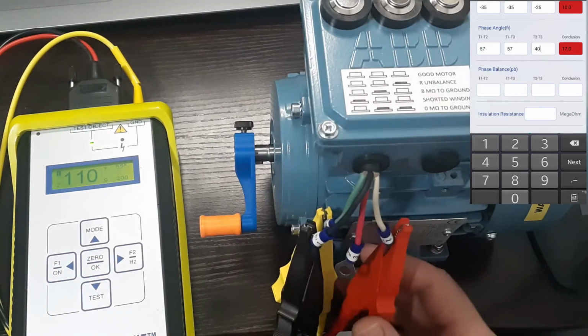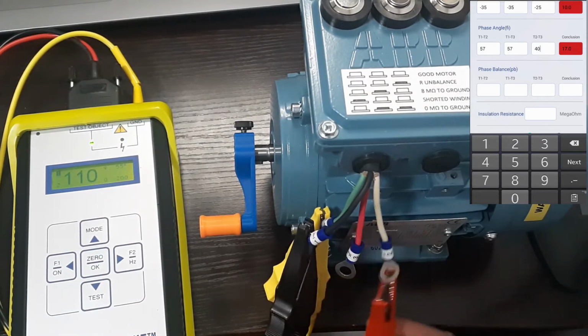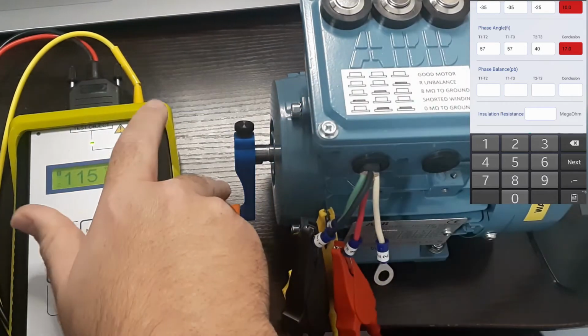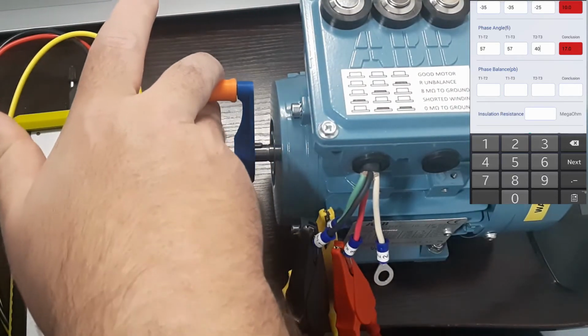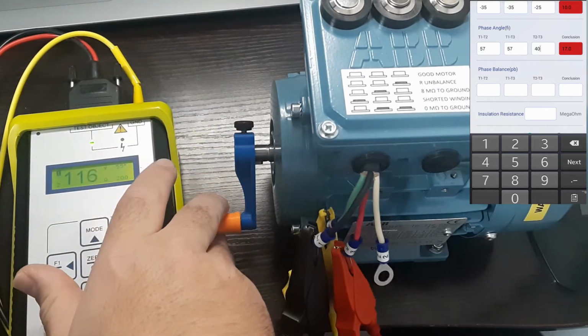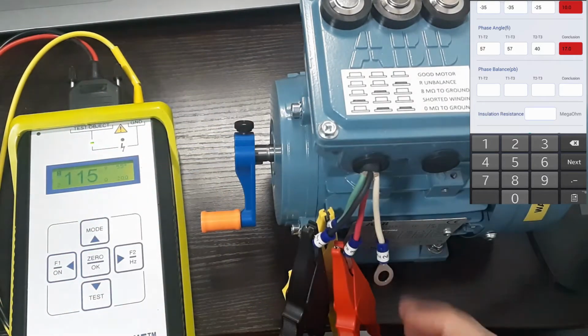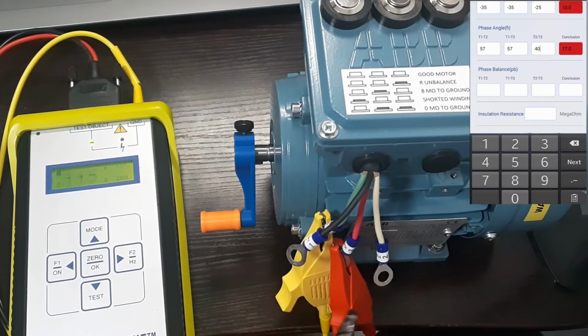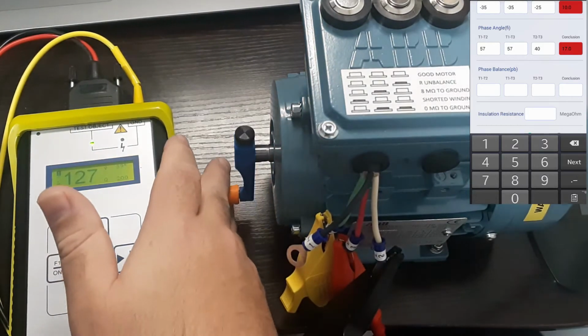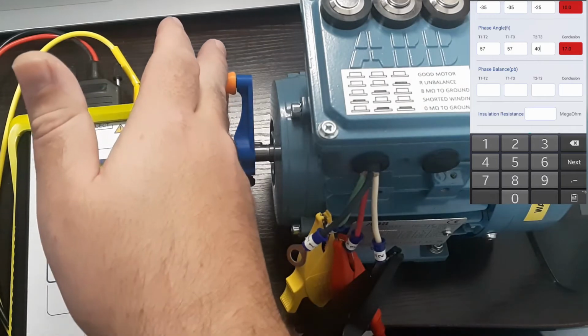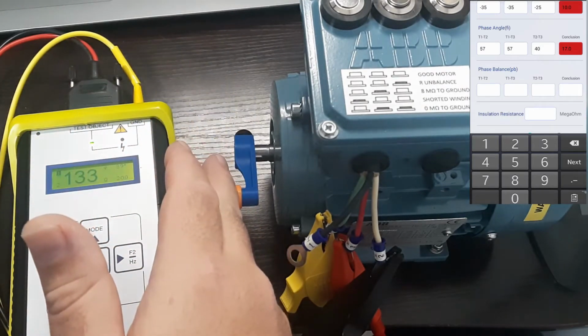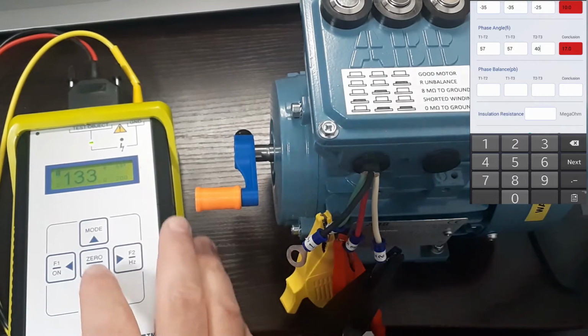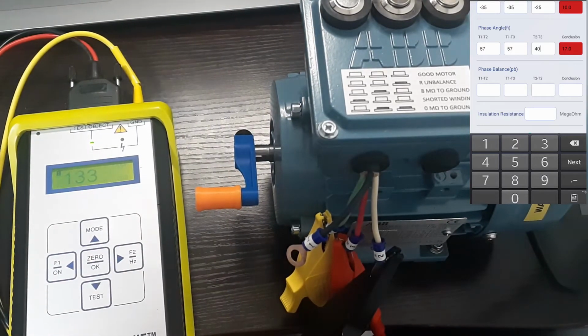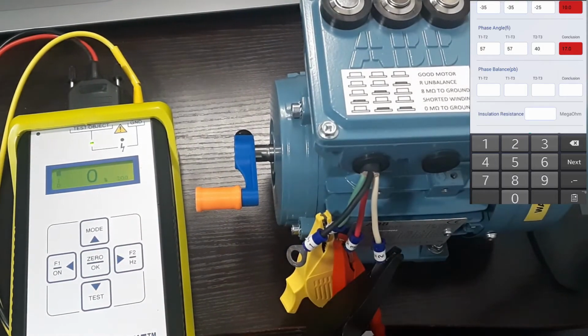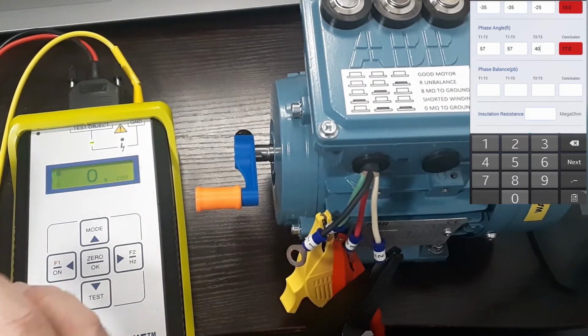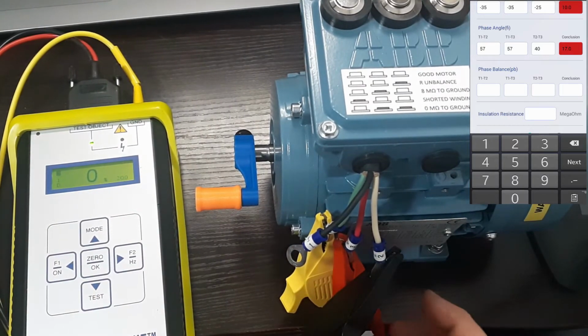So let's go over to 1-3. Oh, 116 on 1-3. And let's go 2-3. 127, that is a very different number. So we'll go 123 and we'll use that as our zero. So we'll put that as our zero there on the phase balance, and we'll test the other phases.